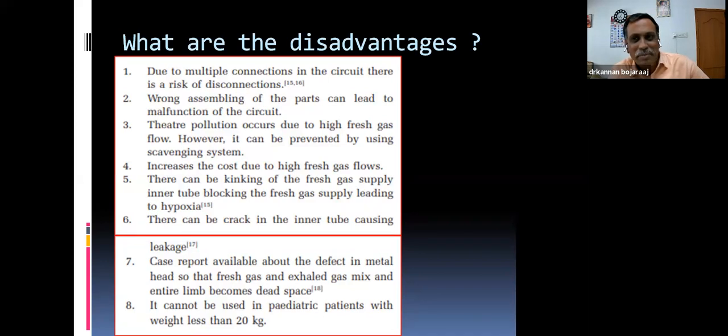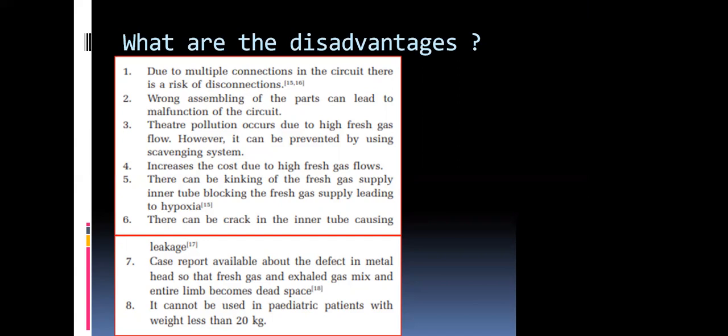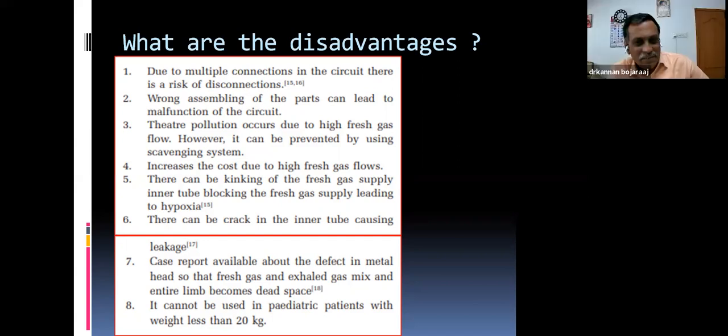pediatric patients? Niveta, can you use this Bain circuit for pediatrics? Can you use it? Yes, sir. Not less than 20 kg. We haven't used it. Why are you not using this for pediatric patients? You can, the bag is so big, but you can attach a pediatric bag of 0.5 liter.